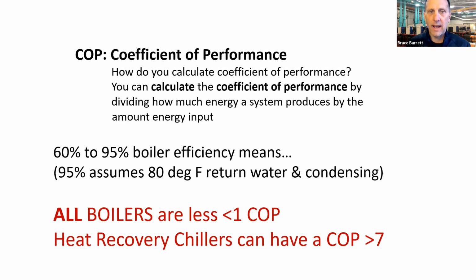Some basic facts: there's a COP, or the coefficient of performance or efficiency of a boiler. They can range anywhere from 60 to 95%. All boilers are always less than a 1 COP. And in the heat recovery world, we're using extracted heat and the heat of compression. We can get COPs greater than 7, times greater than what your best boiler on the planet can do.